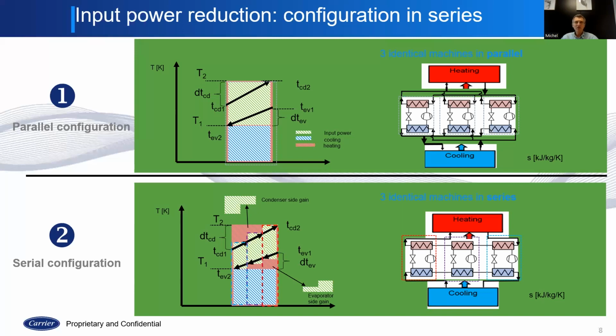Well, temperature is not the same for each evaporator and condenser of each machine. The cycle becomes a little bit funny, because the machine which sees the lowest leaving water temperature, let's say this one, will also have the lowest condensing temperature. So it will have a smaller green area, which represents input power, than equivalent in the top view.